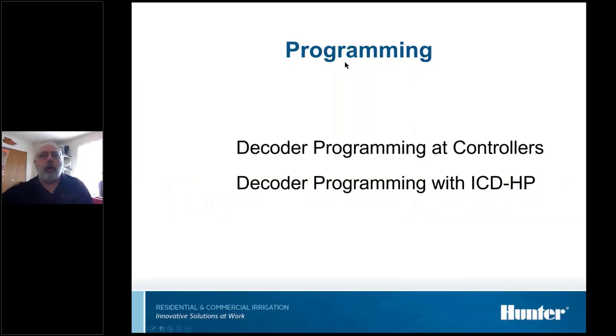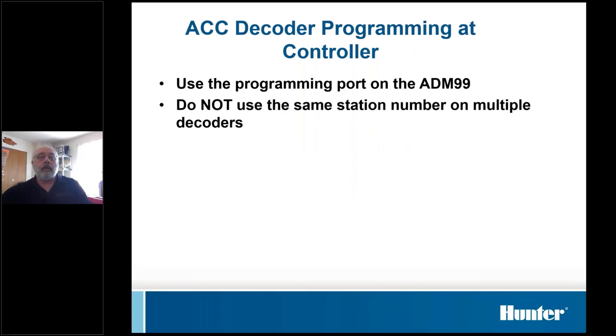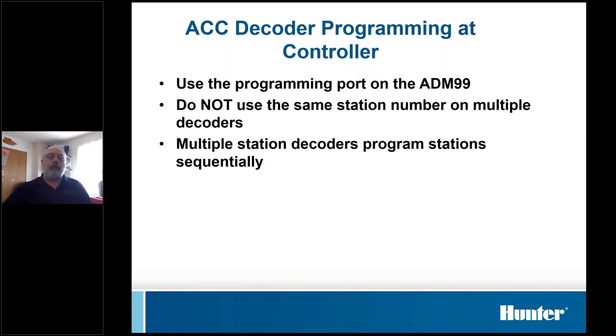So we're going to run you through programming of the decoders, both from the controllers and using our handheld programmer. So the ACC controller, and this is programming at the controller, not with the handheld. You cannot, in any case, program two decoders with the same station number on the ACC decoders. Because of the two-way communications, if it has two decoders with the same address, when we turn an address on, they both answer back to the controller at the same time. The controller doesn't understand what it just heard, and it sends an off command to them, and then just skips them and moves on to the next thing. So you definitely can't have two decoders with the same station number.